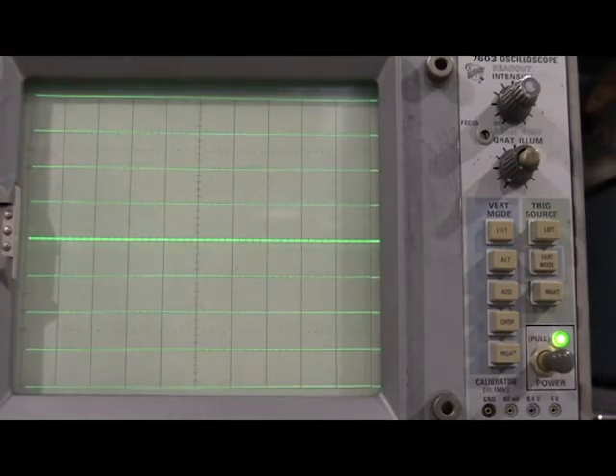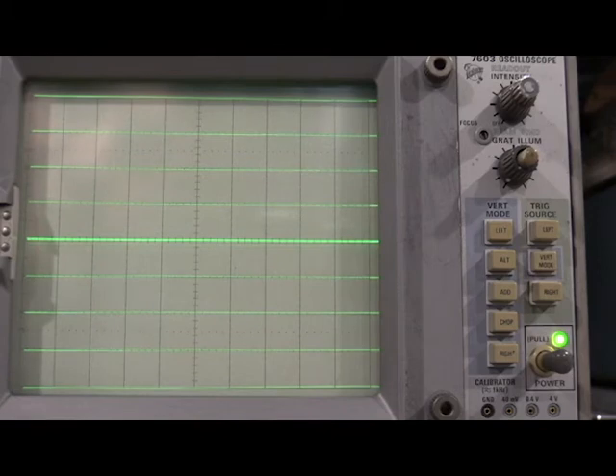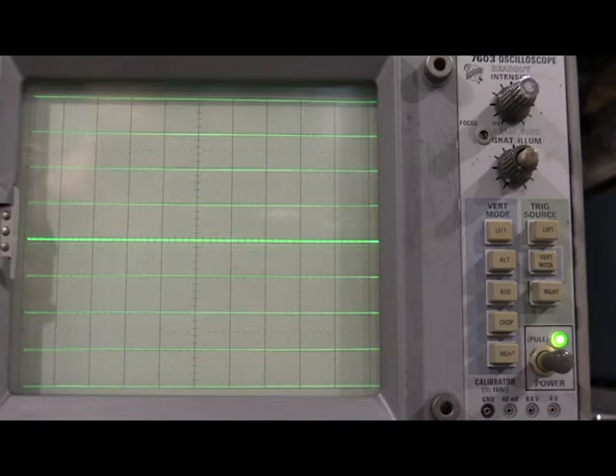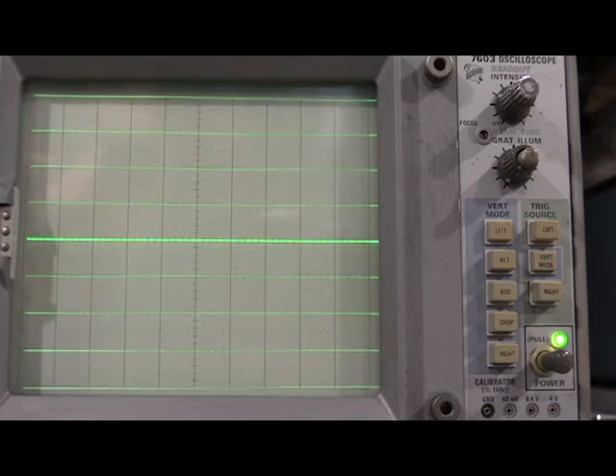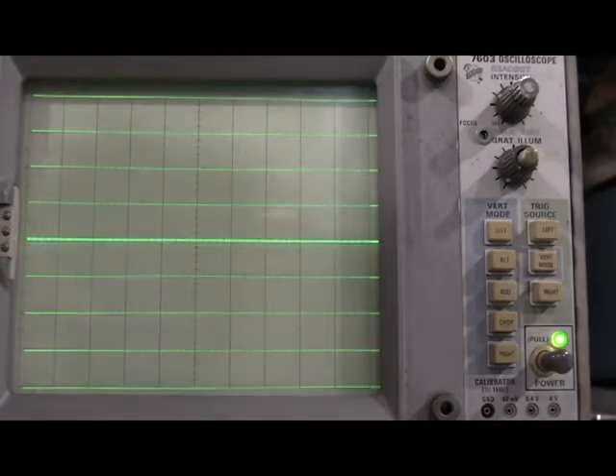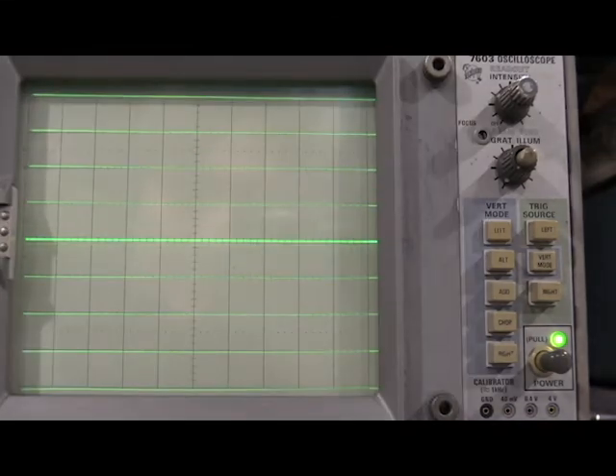So just checking the vertical gain adjustment. Okay, so I'm adjusting the vertical gain. I just need to line up all of these, get everything squared away. This scope is actually so far in really good shape. This may have had the factory calibration on it. Everything's real close. I'm going to call that good.